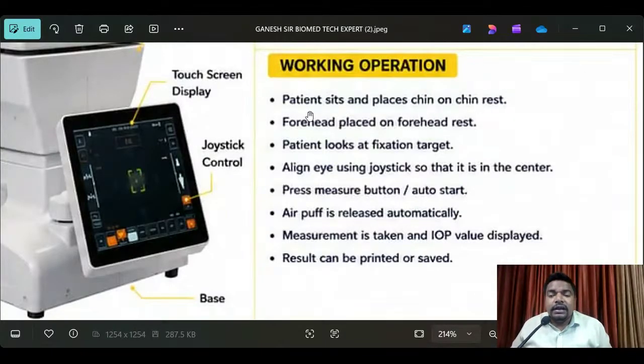See here, the patient sits and places the chin on the chin rest. Understand? Next, the forehead is placed on the forehead rest, and the patient looks at the fixation target. Align the eye using the joystick so that it is in the center, and press the pressure measure button or auto start, and the air puff is released automatically. The measurement is taken and the IOP value is displayed. Results can be printed or saved.